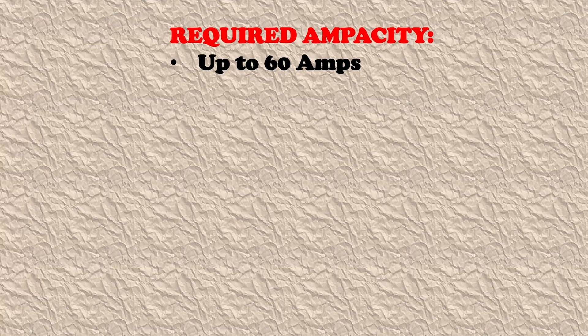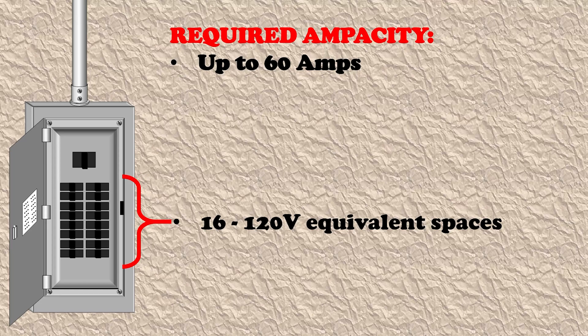The first situation we're going to look at is where our required ampacity is up to and including 60 amps. If we have up to and including 60 amps, we don't need to concern ourselves with whether there's a central electric furnace provided for — this just covers all situations. We are required to have 16 120-volt equivalent spaces, meaning 16 single pole breaker spaces. The code states that at least half of those shall be double pole, and subrule one requires space for two 35-amp double pole breakers, all included in these 16 120-volt equivalent spaces.